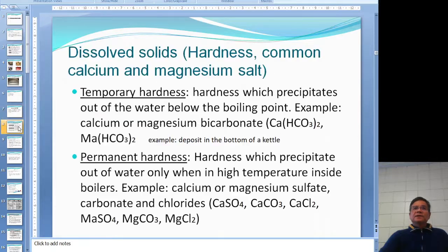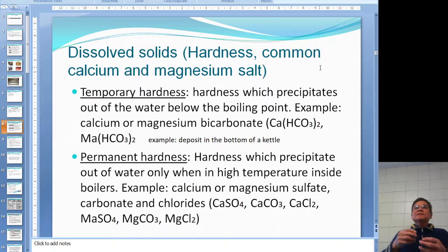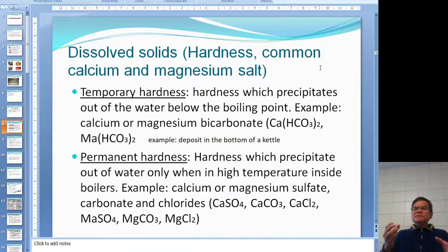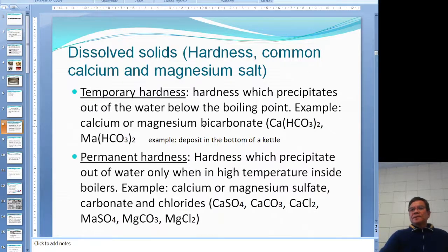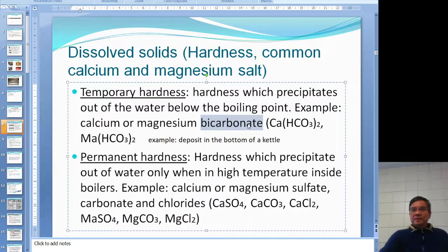If you don't remove suspended solids, they will stick to the heating surface and cause a loss of economy and safety. Dissolved solids are different — they dissolve in the water. This relates to water hardness. There are two types: temporary hardness, which precipitates out when you heat the water slightly, mostly as bicarbonates like calcium bicarbonate and magnesium bicarbonate.